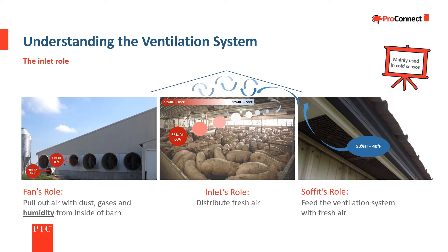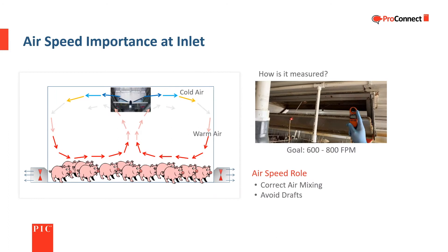Inlets should evenly distribute fresh air to the pigs. The speed of the air passing through the inlet needs to be correct to ensure the cool air entering mixes correctly with the warm air in the room. The goal for inlet air speed is 600 to 800 feet per minute to ensure correct mixing before the air reaches the pig level and to avoid drafts that can chill the pigs.